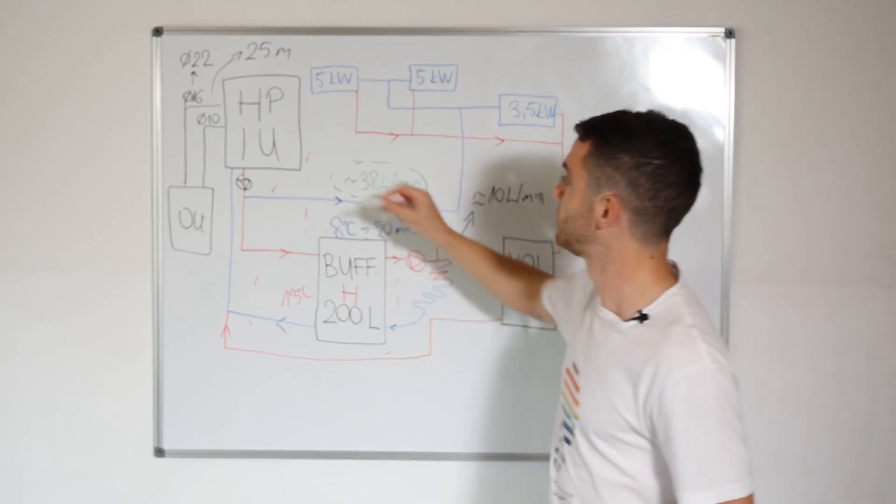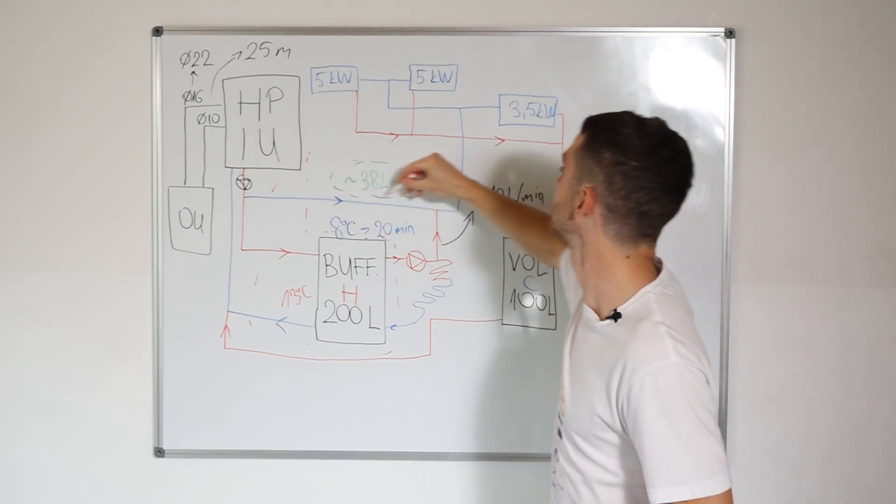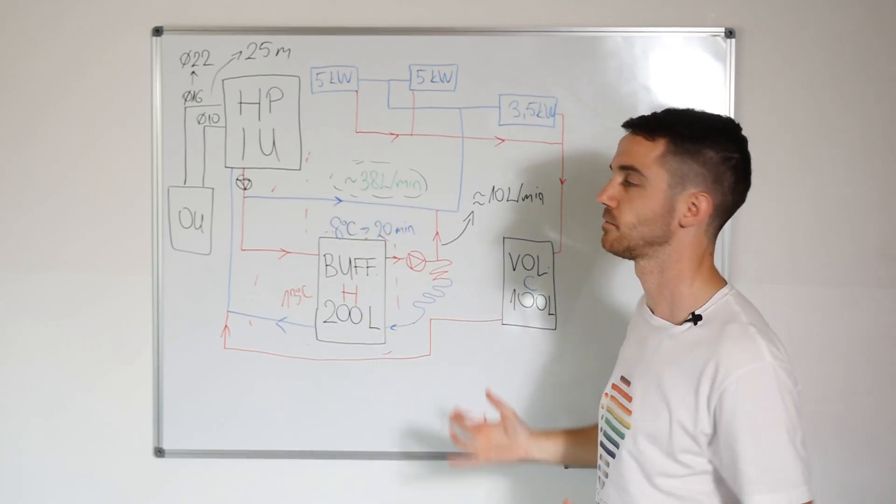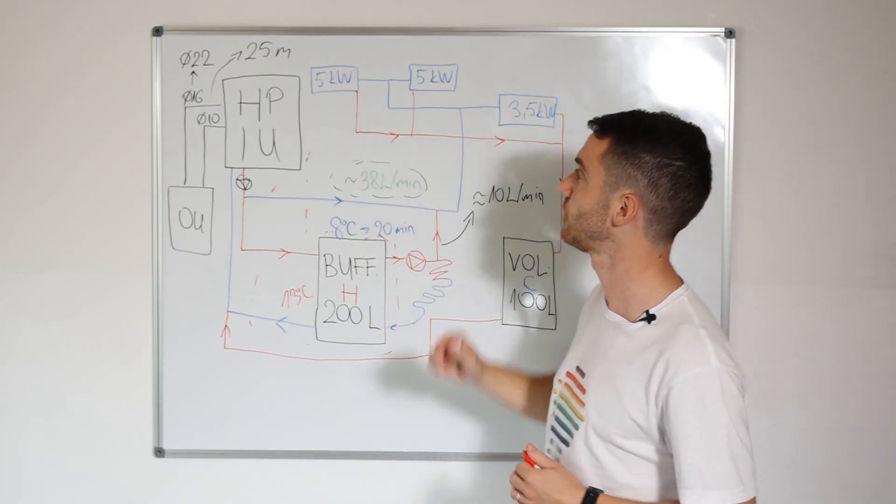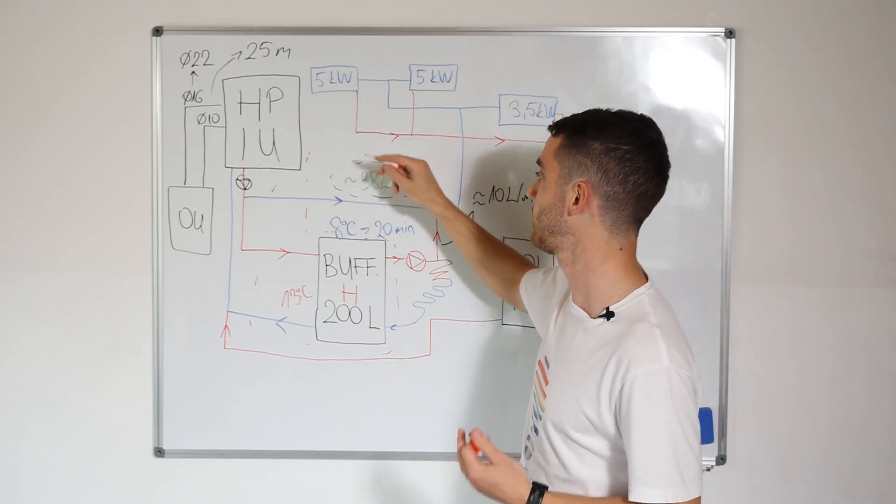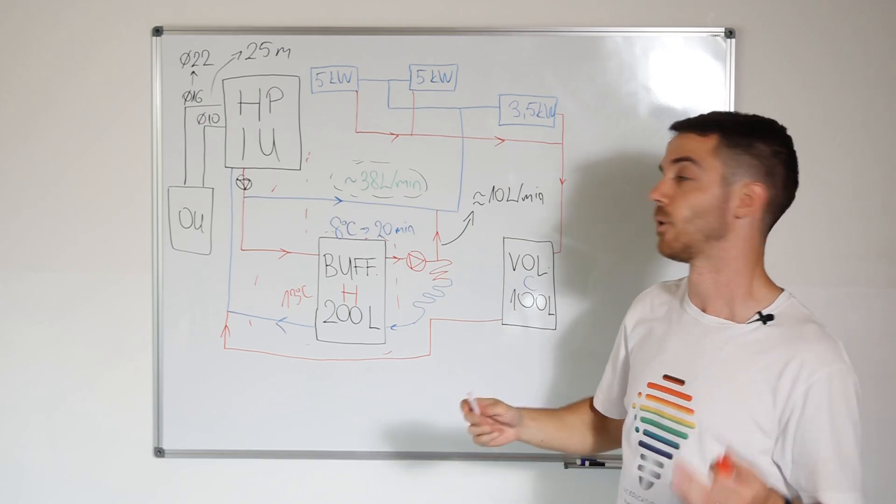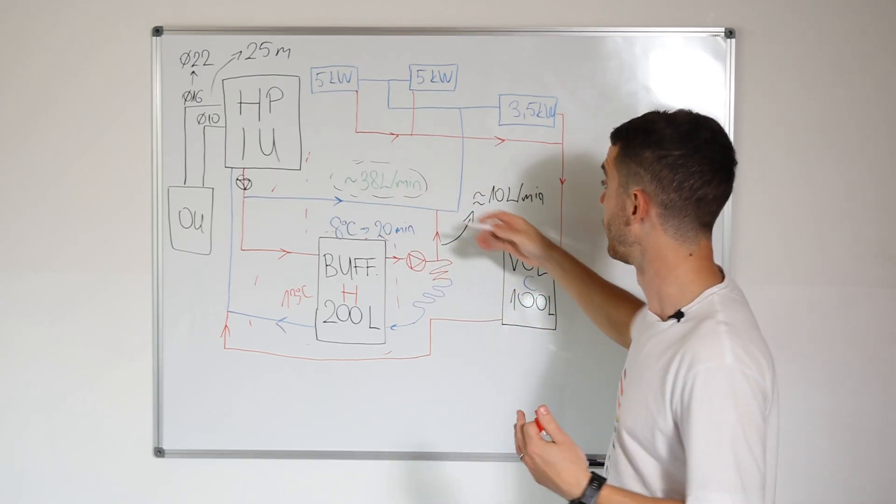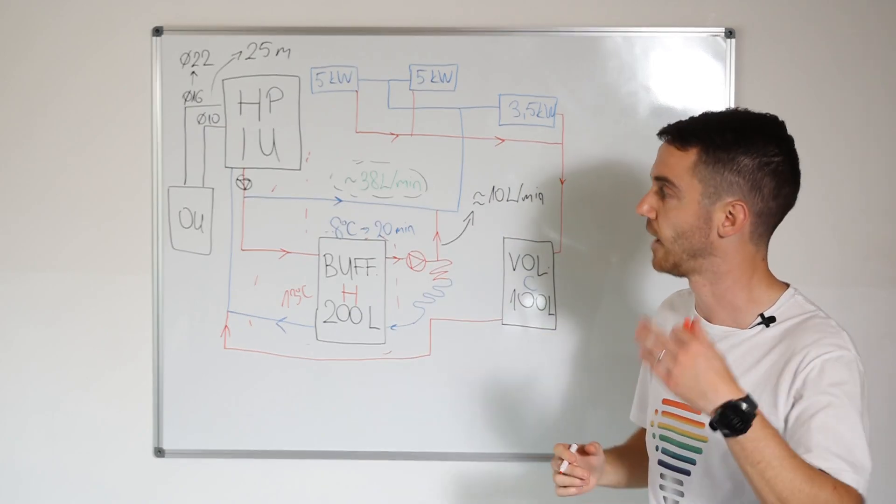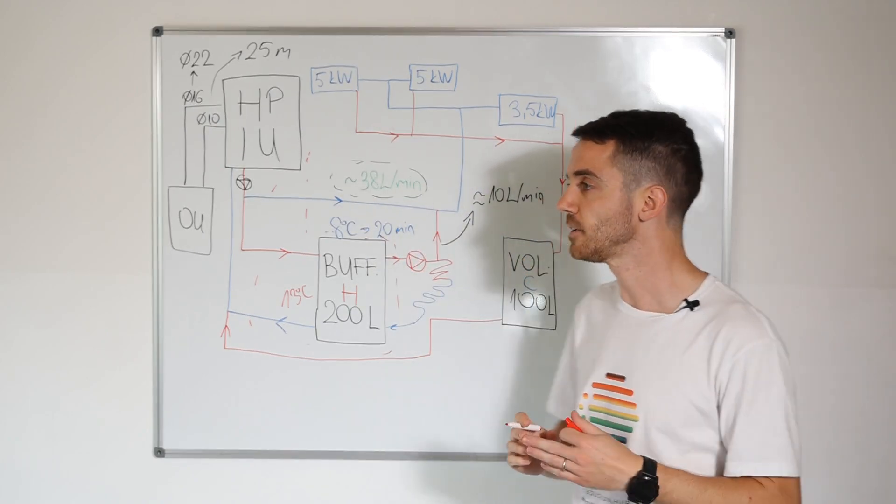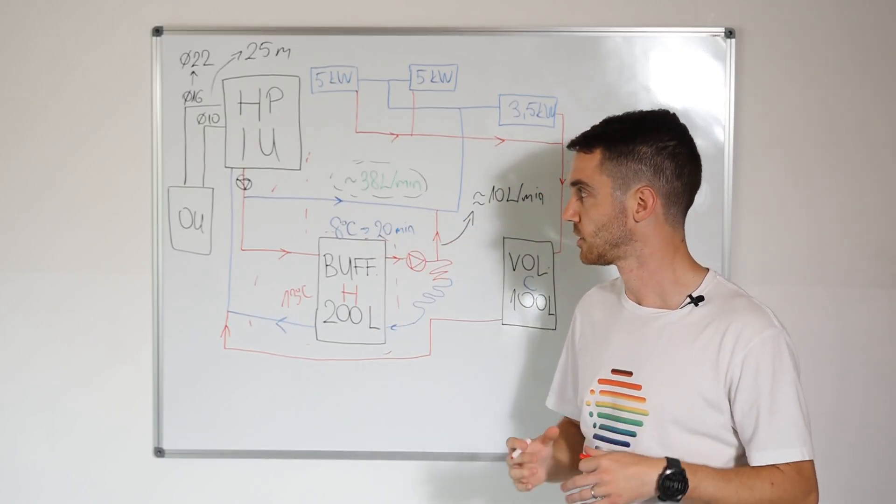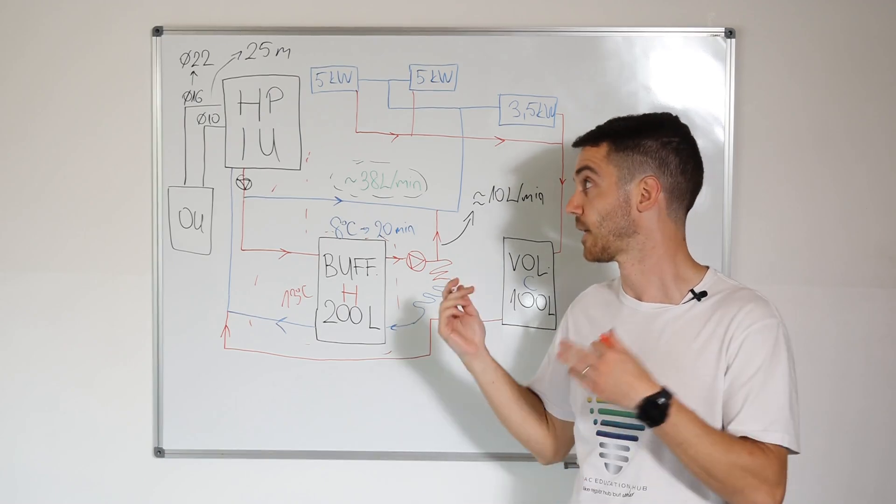At the point when this pump must control fan coils or for heating radiators, whatever, in that case fan coils, it's mandatory to ensure enough flow rate and enough volume. Because with lower volume and in this case with lower flow rate and with low refrigerant charge, after a while they filled the refrigerant, you can read that your temperature on heat exchanger will be too cold and you will have the case like we have here.